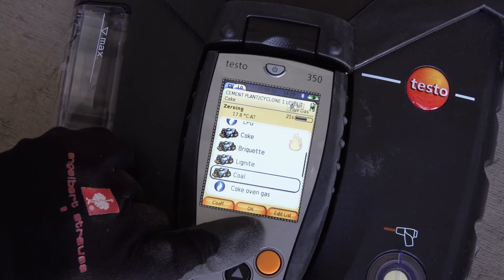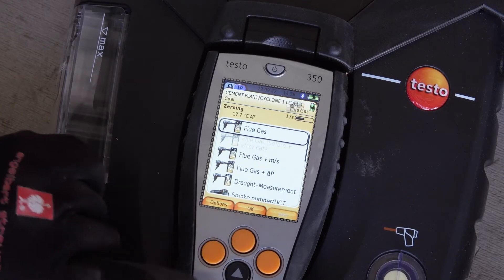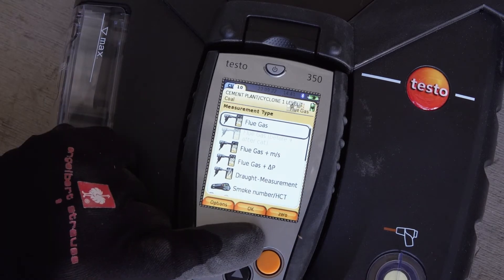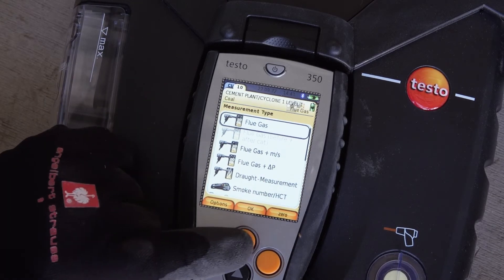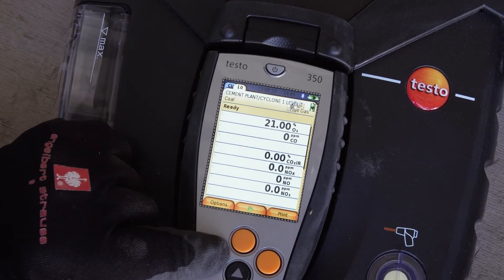The Testo 350 is ready for use within a few minutes and the measurement can be started. Zeroing of the gas sensors is performed before a measurement — the zero point and drift of the sensors are checked, and the O₂ value is set to 21% O₂. Make sure that the ambient air is free of interfering gases such as CO or NO during the zeroing phase.